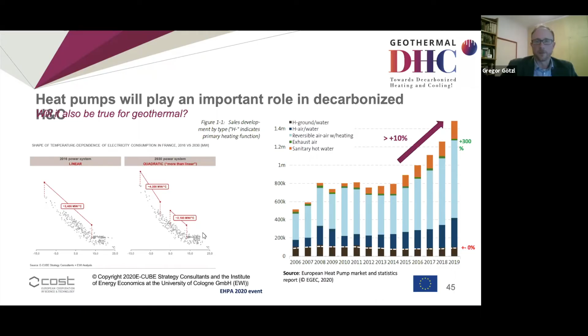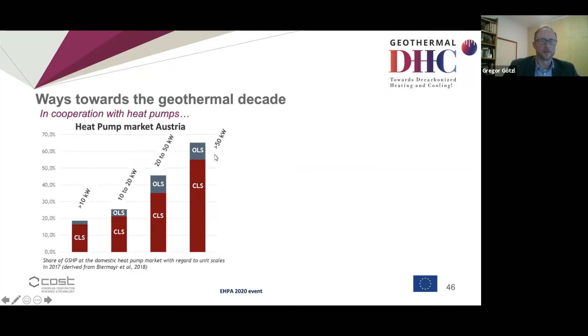If you look at the Austrian market, this is an example where geothermal or ground source heat pumps are still very important. If you look at small scale systems - I mentioned before 12 kilowatt as an average - you see it's clearly dominated by aerothermal systems, 80% plus. But if you go to the larger scale, because there are also technical limits for aerothermal, at the moment we have a share of more than 60% by ground source.